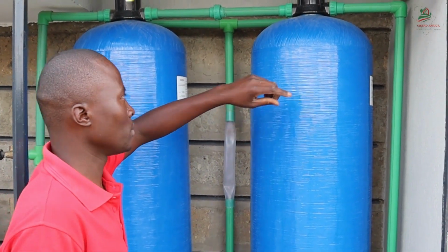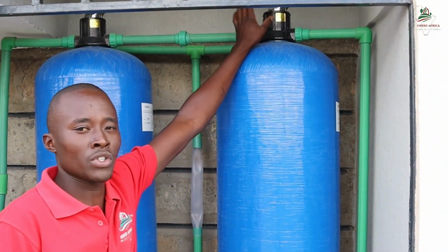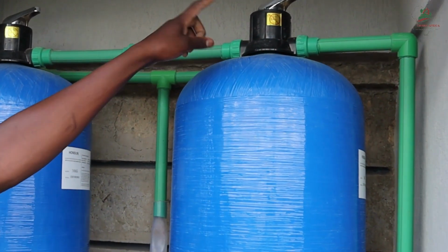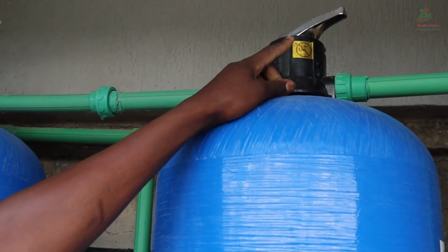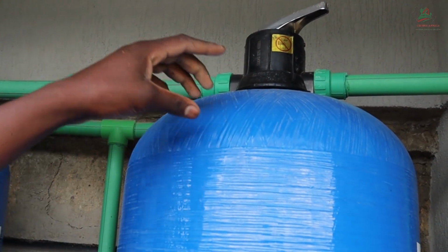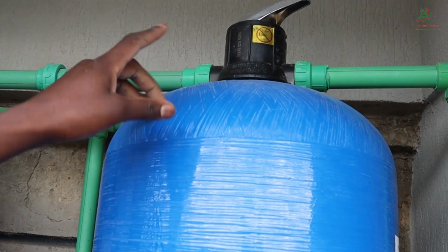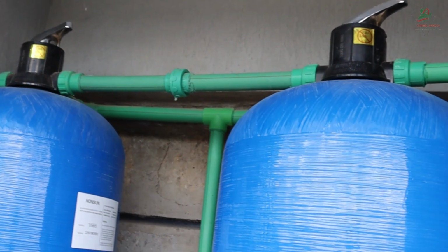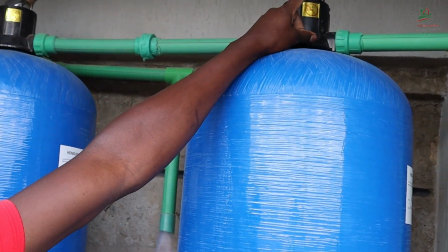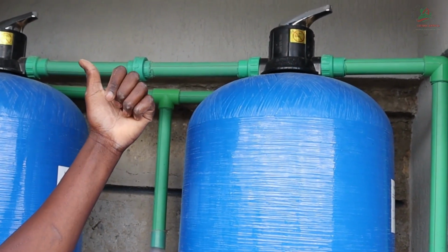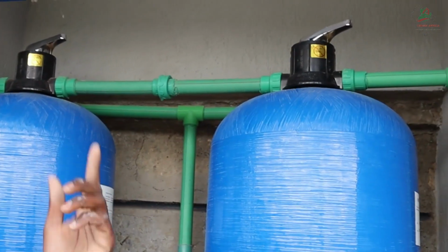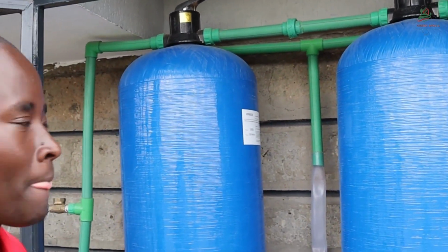What you normally do is backwashing using these gears. You rotate these gears. At this line, you can see that when this gear is facing that side, it means it is on the filtration system. On the filtration system, water is allowed to pass through all the way to the next stage of the process. But if you turn this valve this side, you switch it to backwash, meaning it reverses water from the other side to remove those trapped sediments.